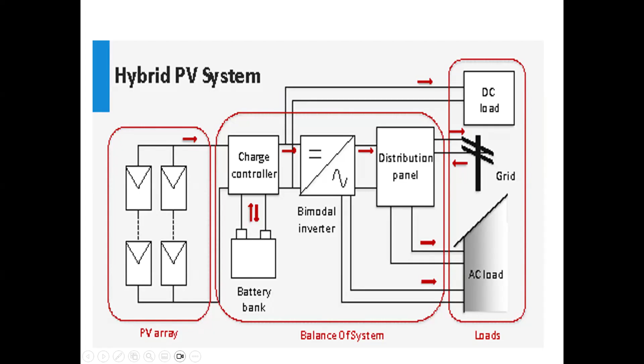The battery bank capacity can be determined according to our requirements, based on which devices need to be powered during a shutdown period when KSEB supply is not available. Based on that, we can design the required battery bank capacity. So here, similar to before, we have the PV array, charge controller, and a bimodal inverter that can operate the distribution panel, DC load, and grid connection. Along with this, we also have a battery bank, that is the only difference.